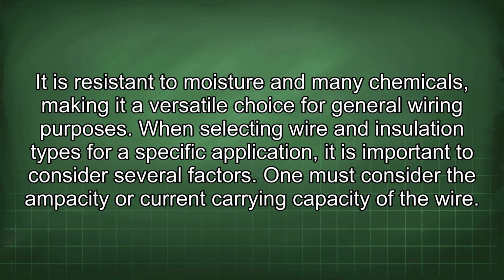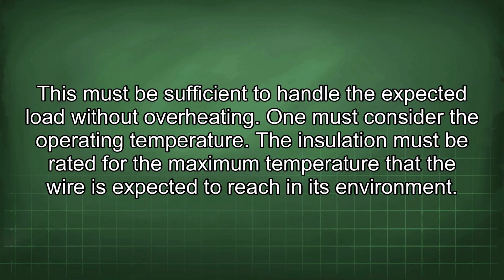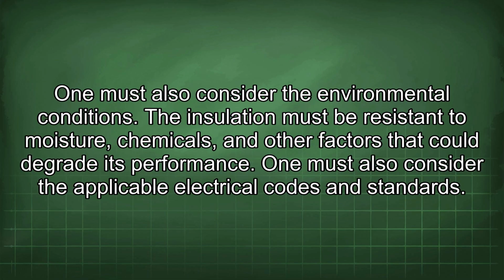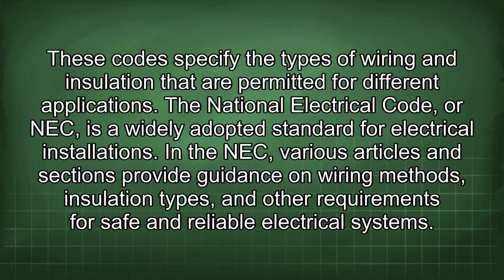When selecting wire and insulation types for a specific application, it is important to consider several factors. One must consider the ampacity, or current carrying capacity, of the wire. This must be sufficient to handle the expected load without overheating. One must consider the operating temperature. The insulation must be rated for the maximum temperature that the wire is expected to reach in its environment. One must also consider the environmental conditions. The insulation must be resistant to moisture, chemicals, and other factors that could degrade its performance. One must also consider the applicable electrical codes and standards. These codes specify the types of wiring and insulation that are permitted for different applications.